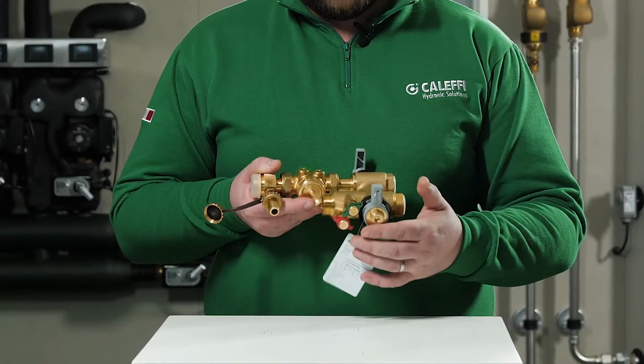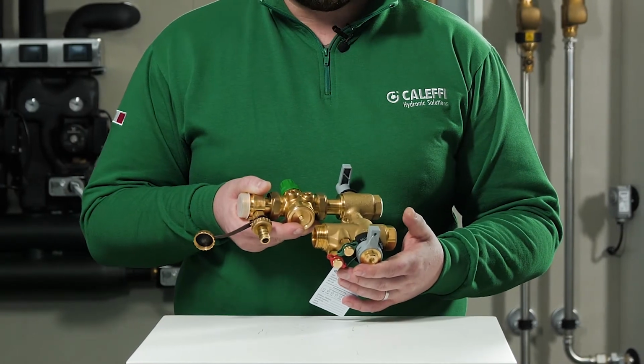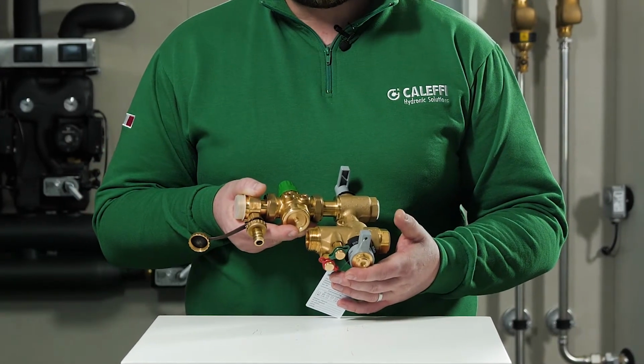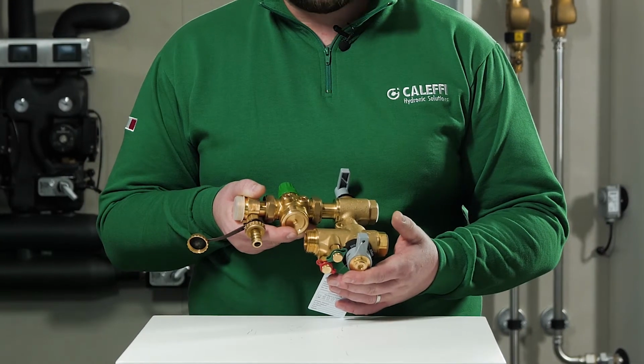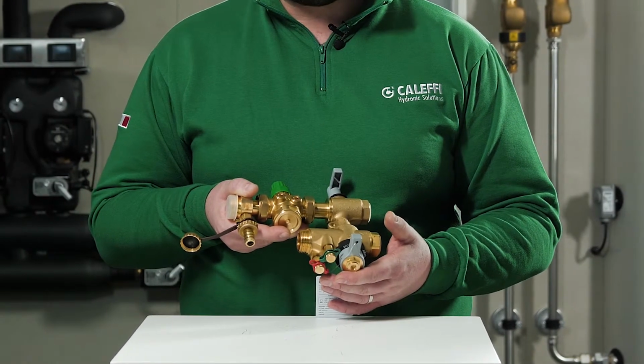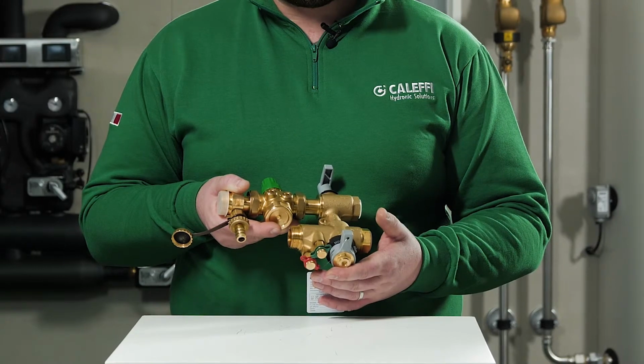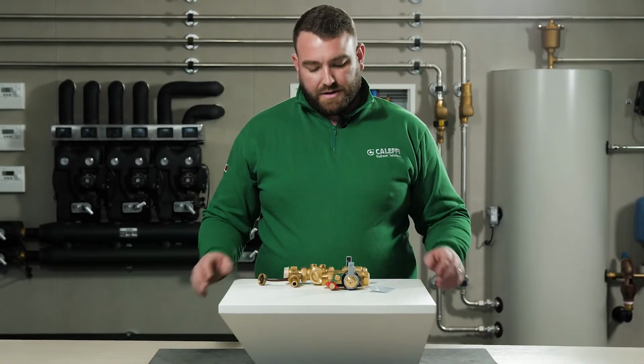Using the venturi profile, it is possible to check the flow rate through the unit. Venturi profile has a fixed kV. Because of this, with the help of the measuring station, it is possible to measure the total flow rate and its set desired value. Finally, we'll talk about the strainer in the unit.